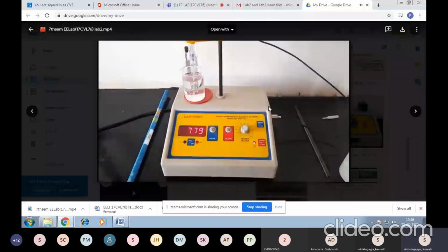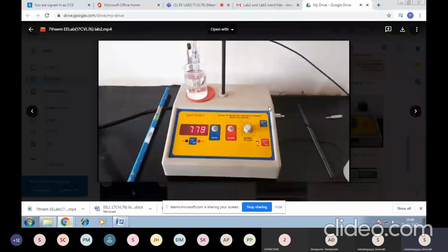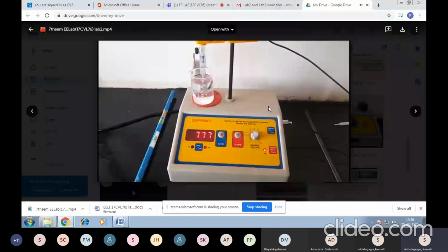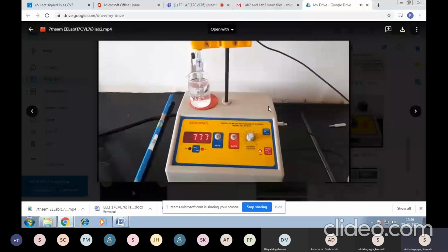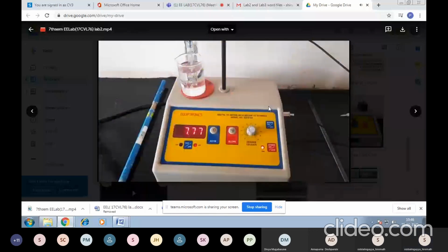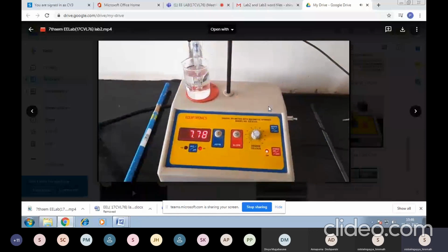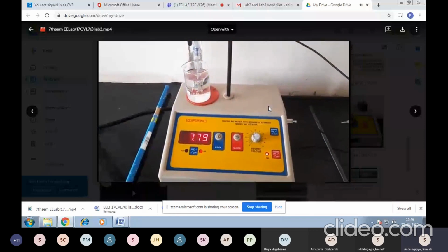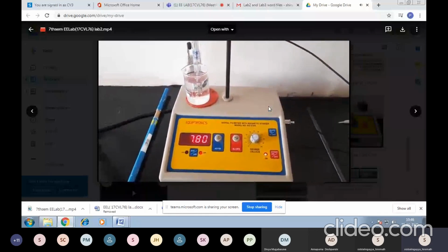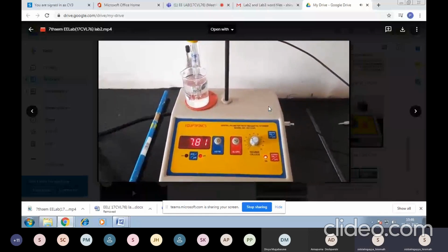Now, the third step in calibration is the combined electrode. The BNC plug is to be connected to the BNC female marked electrode, that is on the side. Temperature knob: the EMF generated by the electrode is temperature sensitive. This control compensates for temperature dependence of electrode output. The dial has to be set to the marking corresponding to the temperature of the solution under test.